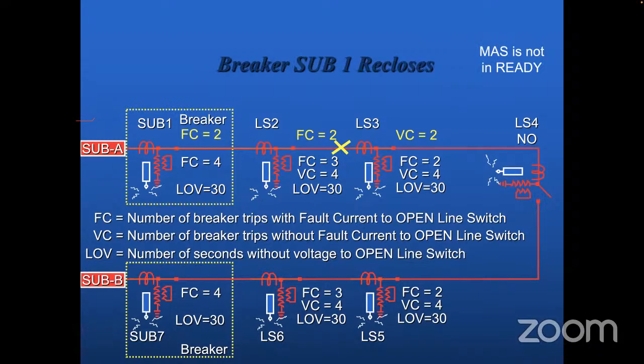Again it's trying, thinking maybe it's a temporary fault, closing in - but the fault still exists. Now our current count is FC equal to 2 here, FC equal to 2 here, and VC equal to 2 here. So voltage, no voltage, and no fault current. The number of breaker trips without - because it's seeing no voltage here, and also seeing no fault current - that's how it's detecting this VC, and everything is local. There is nothing right now, no coordination. This is just tripping, and these are all local agents measuring local values and increasing their counters.